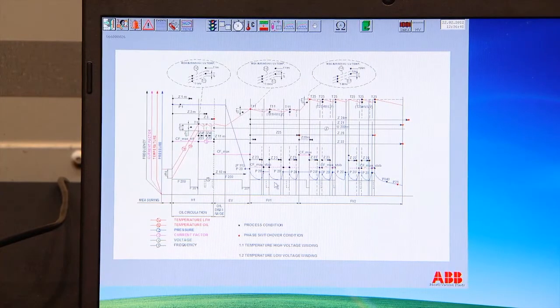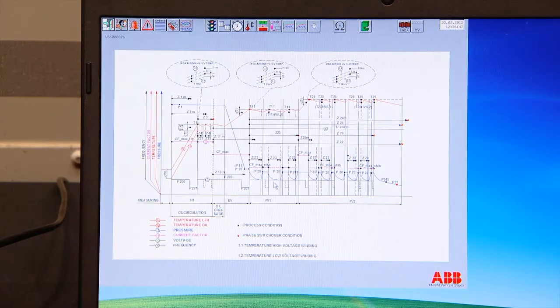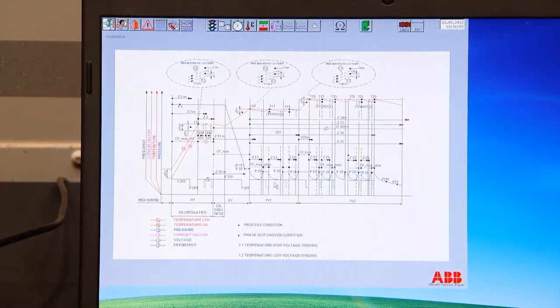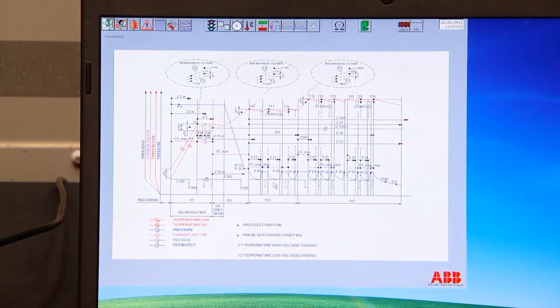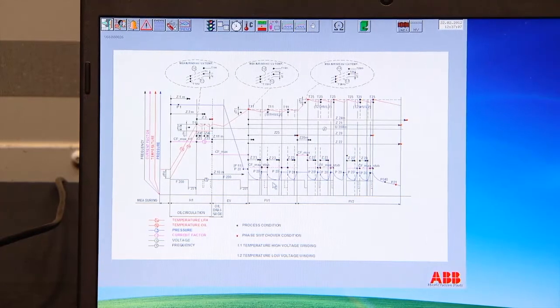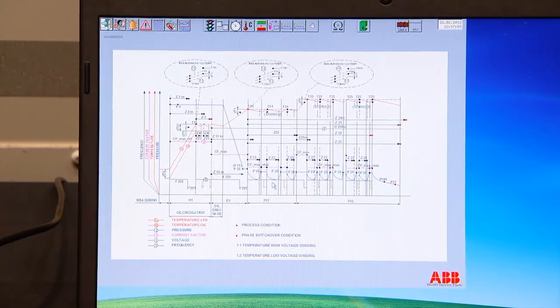Not really. At those levels, at 90 and 100 degrees, you're going by experience based on the size of the transformer. Bigger transformers, then you need to do more cycles. Smaller transformers, then you do fewer cycles. So let's say a 100 MVA transformer, maybe you can dry out in 4 days. A 750 MVA you have to dry out in 7, 8, 9 days. And this time span difference is taken at 90 degrees and 100 degrees.